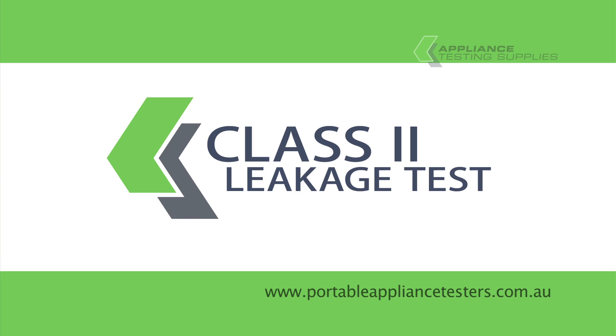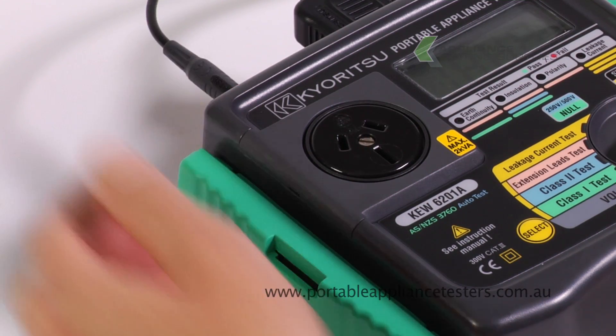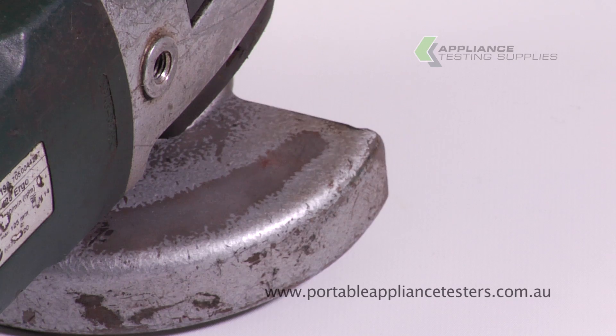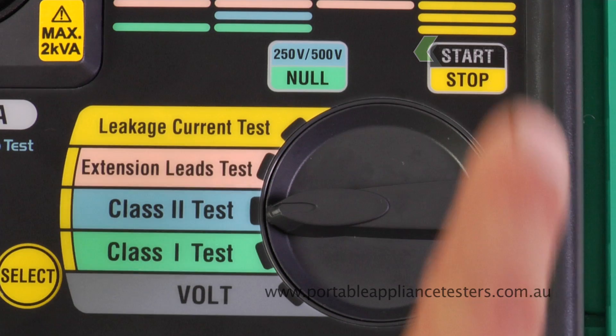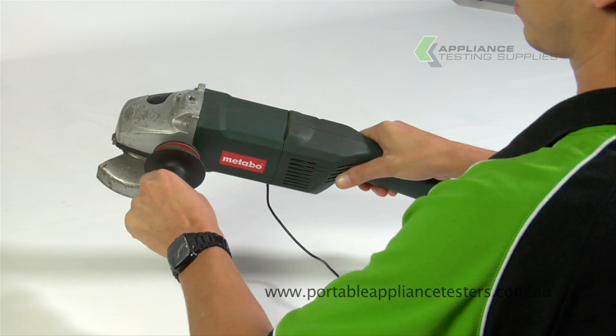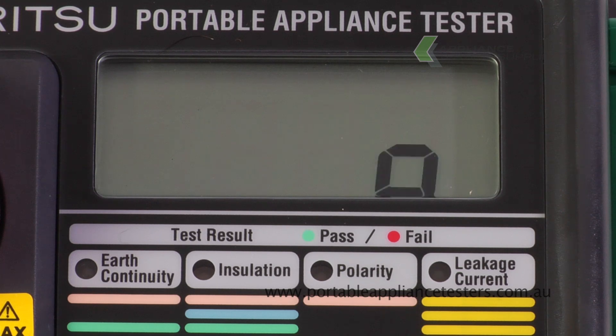Class 2 earth leakage testing. Plug the earth bond lead into the top of the appliance tester. Plug the appliance into the front of the Kyoritsu unit. Attach the crocodile clip to the exposed metal part of the appliance under test. While holding the select button down, turn the dial to Class 2 testing. Press start to continue. Power up the appliance. After several moments, a result will appear on the screen. LED lights will be either green for pass or red for fail.